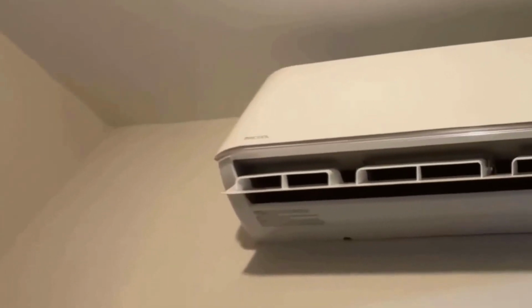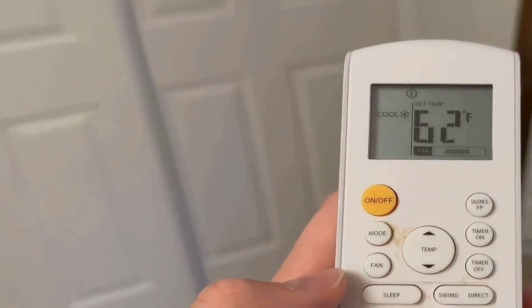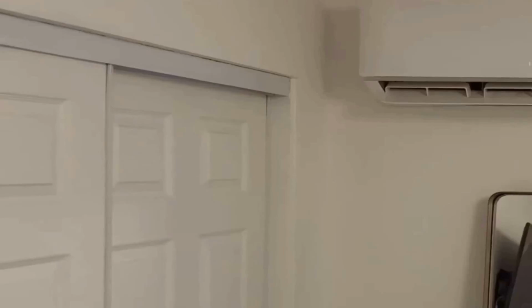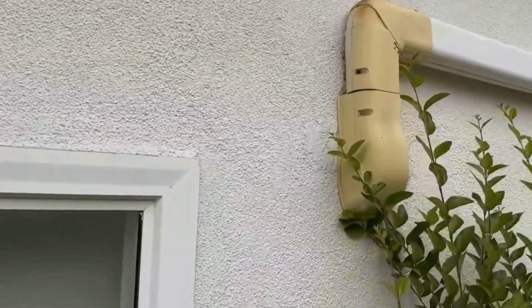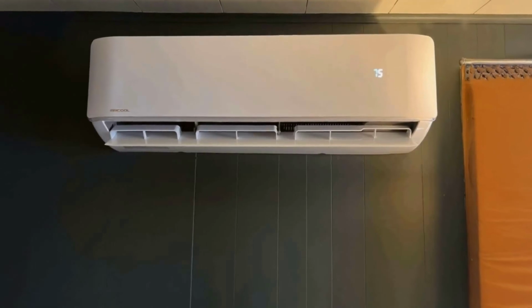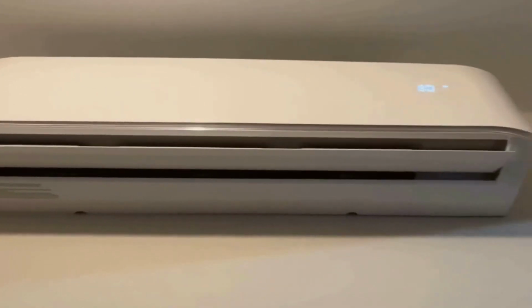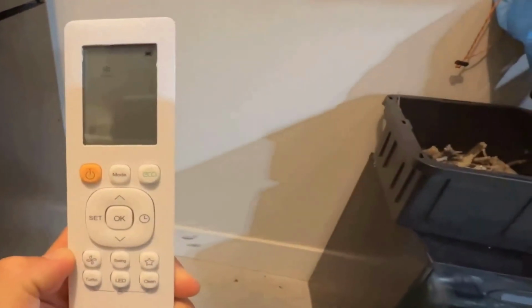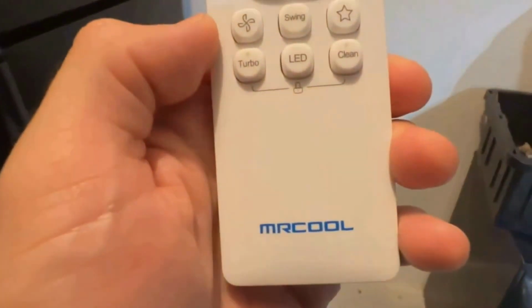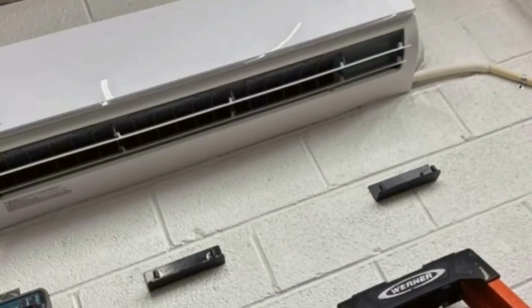I've had this system running for 6 months, and I'm sharing exactly how it's been to install, use, and live with day to day. From my experience, the DIY promise is real, but it's not a one-hour project. I set mine up over a weekend for an open concept space of roughly 950 square feet with high ceilings. I'm reasonably handy, but not an HVAC pro. The biggest time blocks were prepping a level pad for the condenser, drilling a 3.5-inch hole through the wall, and running a dedicated 230-volt circuit to an outdoor disconnect to meet code. I handled most of the work and hired an electrician for the circuit because high voltage is not something I like to guess on. If you've never done this kind of project, think of it as a solid home improvement job, not plug and play.